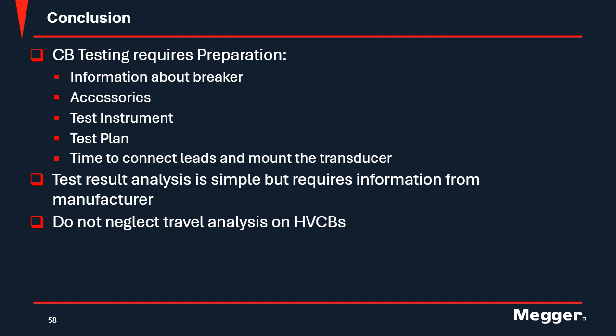Now, sometimes you don't have the opportunity to do some pre-planning before you go out to test. I understand that. But one big thing I do want to stress is that you should not neglect your travel analysis on high voltage circuit breakers. As we saw in that case study, they did just timing the first time. They did not see that B phase had that drastic over travel, and that breaker would have failed in service at some point.